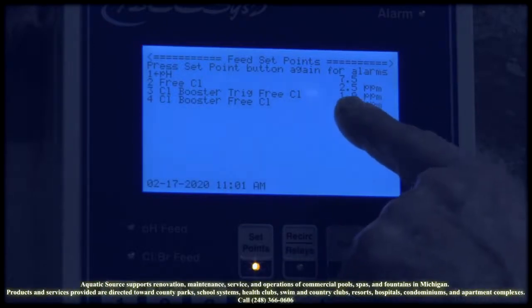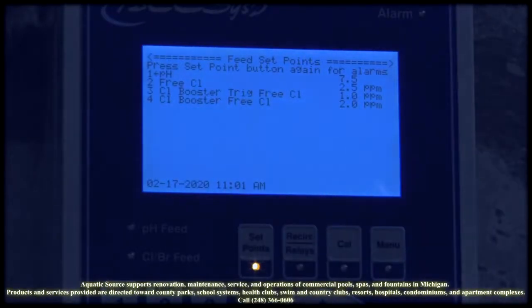We also have a trigger point for booster. If for some reason the salt generator that's making chlorine in the pool drops too low for parts per million, it will automatically turn on a Stenner pump with a liquid chlorine vat to boost the chlorine level and maintain, especially if you have a heavy bather load from a meet or a large meet over the weekend where you're going nonstop all day.